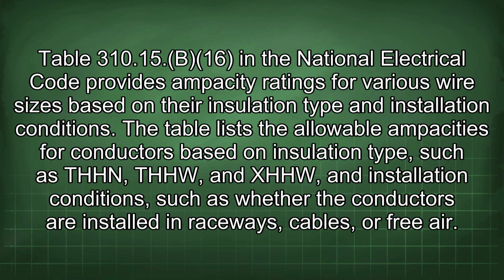Table 310.15(B)(16) in the National Electrical Code provides ampacity ratings for various wire sizes based on their insulation type and installation conditions. The table lists the allowable ampacities for conductors based on insulation type, such as THHN, THHW, and XHHW, and installation conditions, such as whether the conductors are installed in raceways, cables, or free air.